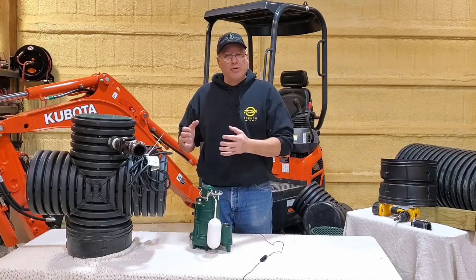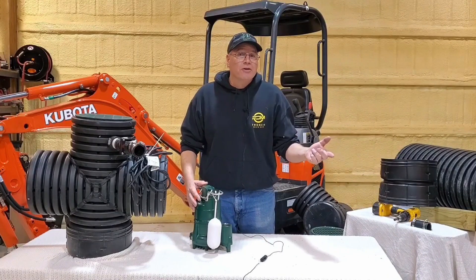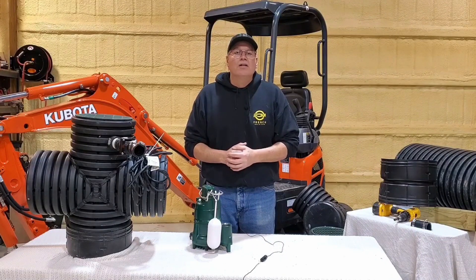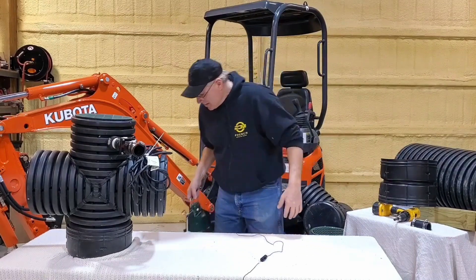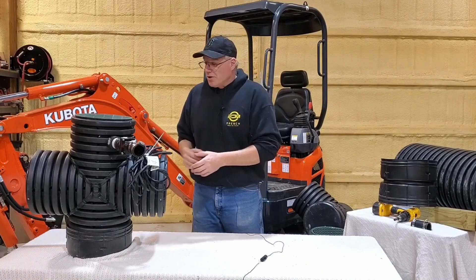As a contractor, if I put in a duplex system versus a single pump system, I know nobody's ever going to call me. They're not going to wake up to a situation where the pump threw the thermo switch, tripped the breaker, and the system failed on the biggest rain event of the year. A duplex protects your property better than anything. Unless it's a very small area that collects and ponds in the back and doesn't harm anyone — in that case, single units are fine.